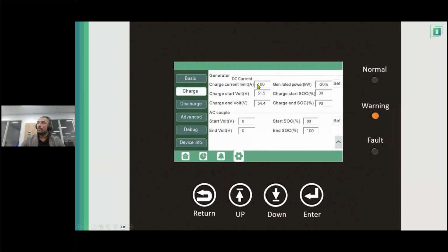And then make sure you state what the DC current going from that generator to charge your battery is going to be. Okay. And when you're stating the rating of the generator, you're going to subtract 20%. Essentially, you don't want to over-throttle the generator and potentially damage it. So doing quick math, if you have a 10K generator, minus 20%, you're going to put 8K here.